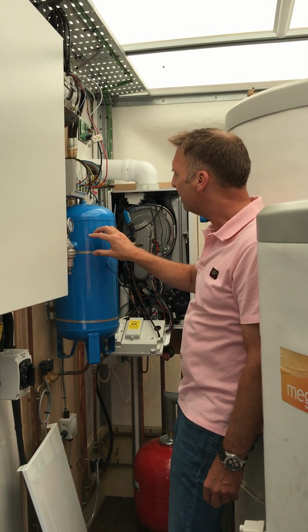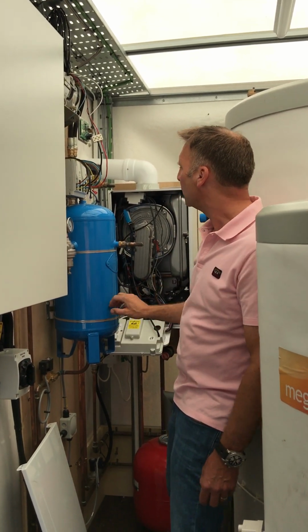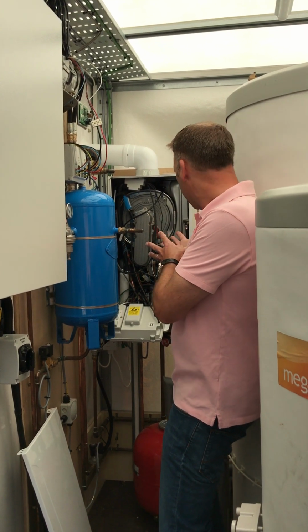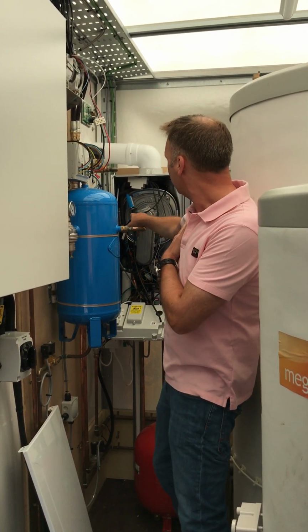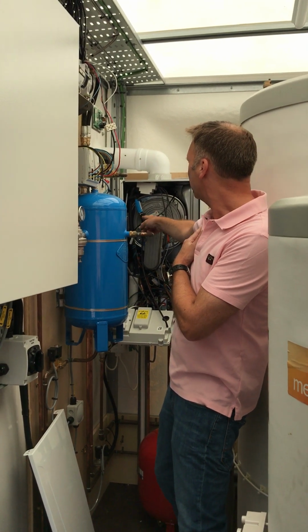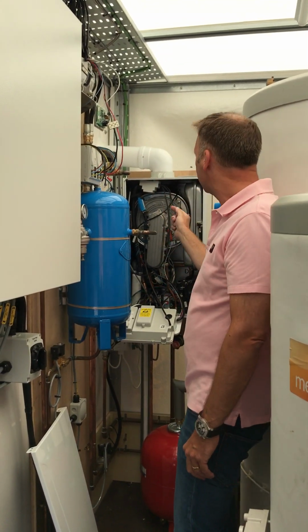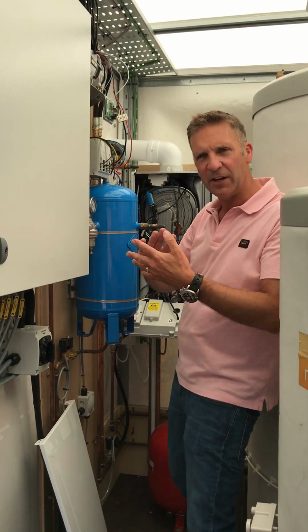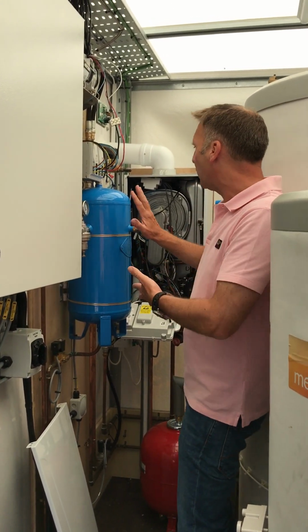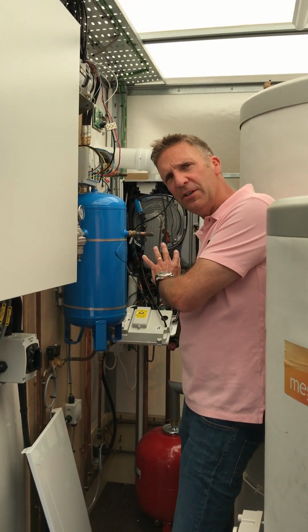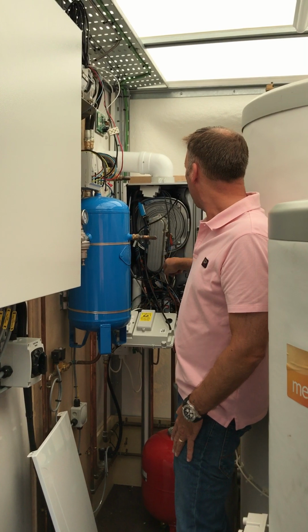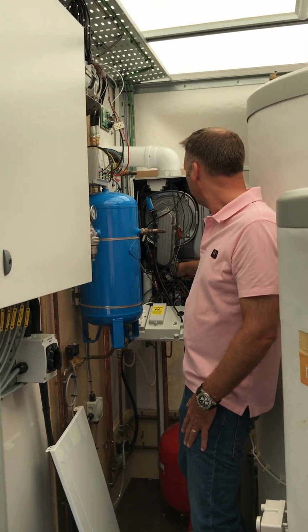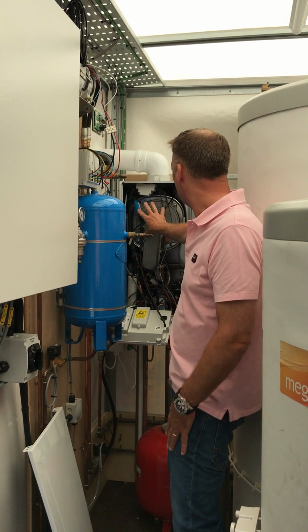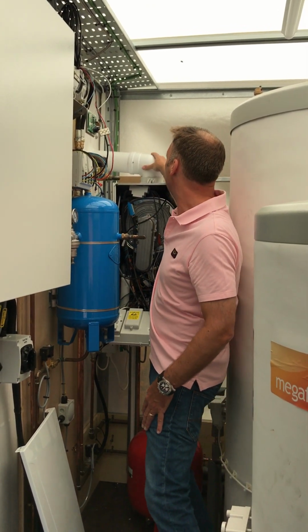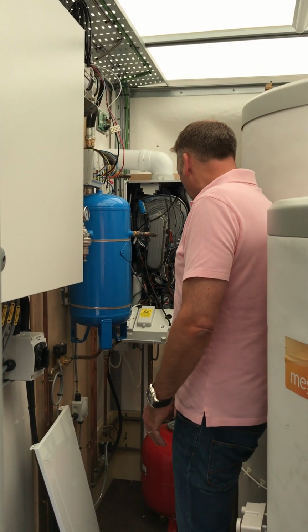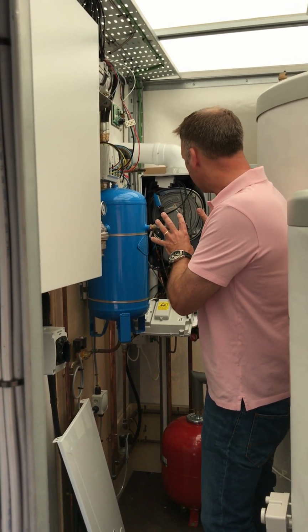So when this tank gets to 4.8 bars of pressure, it sends a signal to the boiler to say, I've got some gas. The boiler then senses here using a UV sensor whether the boiler's lit and sends a signal back. That's creating a handshake. It's all safety systems, because we don't want to be releasing the gas from the HERU unless we're absolutely certain that the boiler's ready for it. Then the gas is released and blended in through here into the combustion chamber of the boiler, and this is the exhaust that comes out of here. And that really deals with the whole gas system.